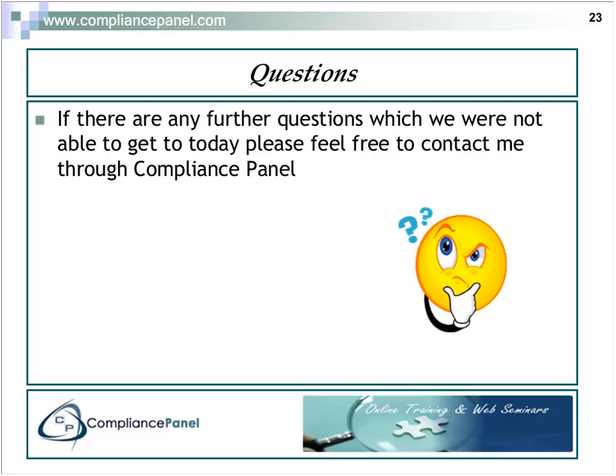But I'd just like to say that in melding your device master record with your device history record together, I've always found it easier if you put a definition up front of what has to be in the device master record and what has to be in the device history record for either each type of device or each individual device, so that someone at the end of the line has a checklist of what has to actually be included, whether it be for the DMR or for the DHR.